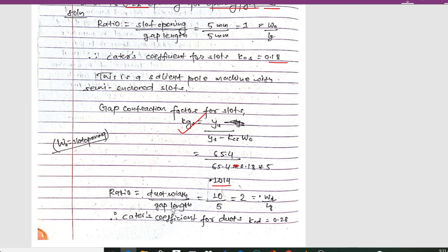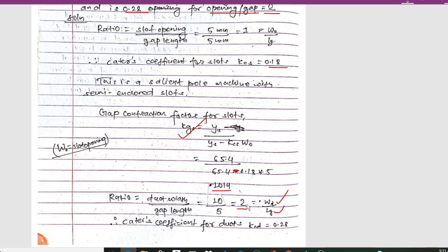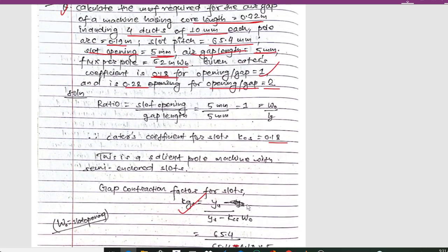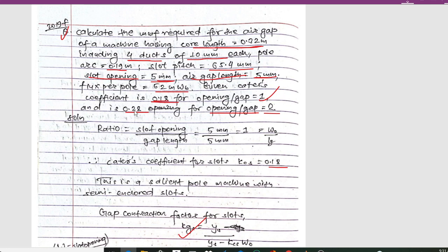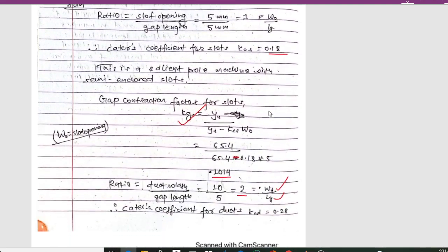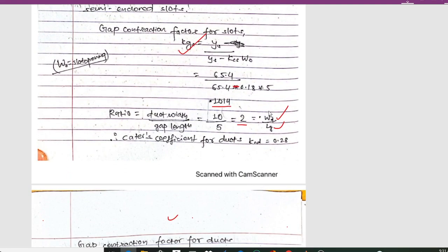For the duct, the ratio = duct width / gap length = 10 mm / 5 mm = 2. For ratio = 2, the Carter's coefficient is 0.28, so the Carter's coefficient for the duct, Kcd = 0.28.